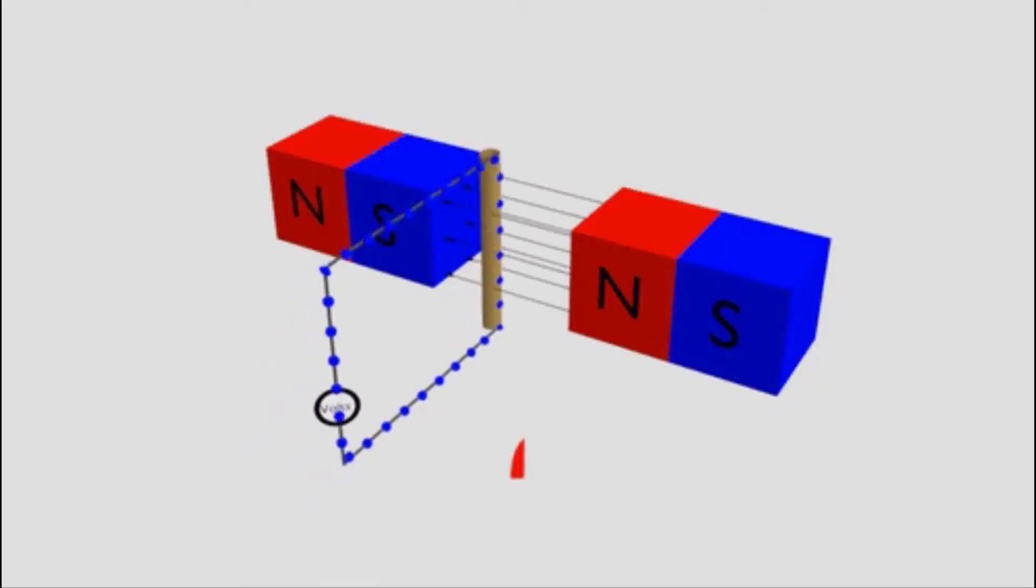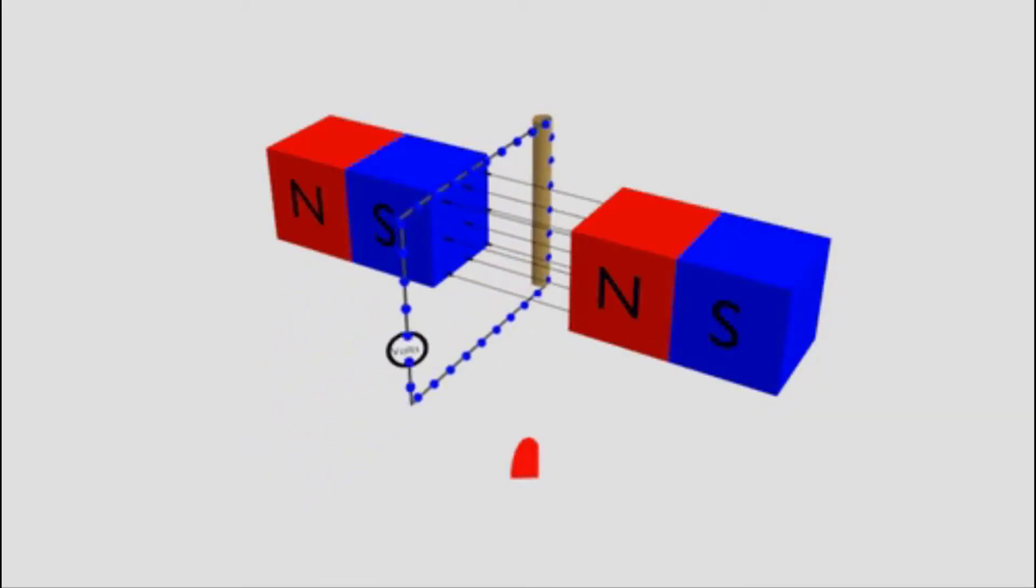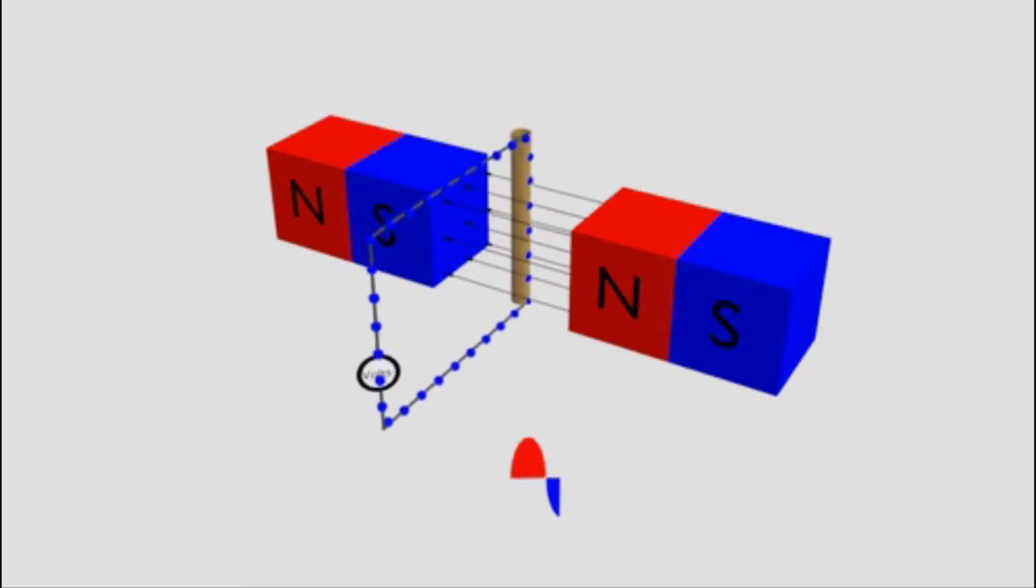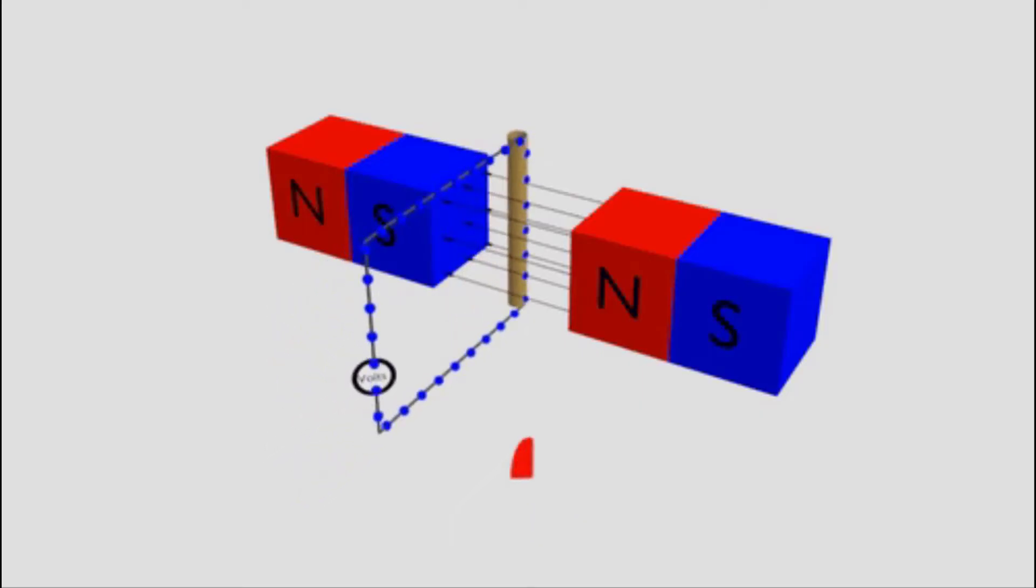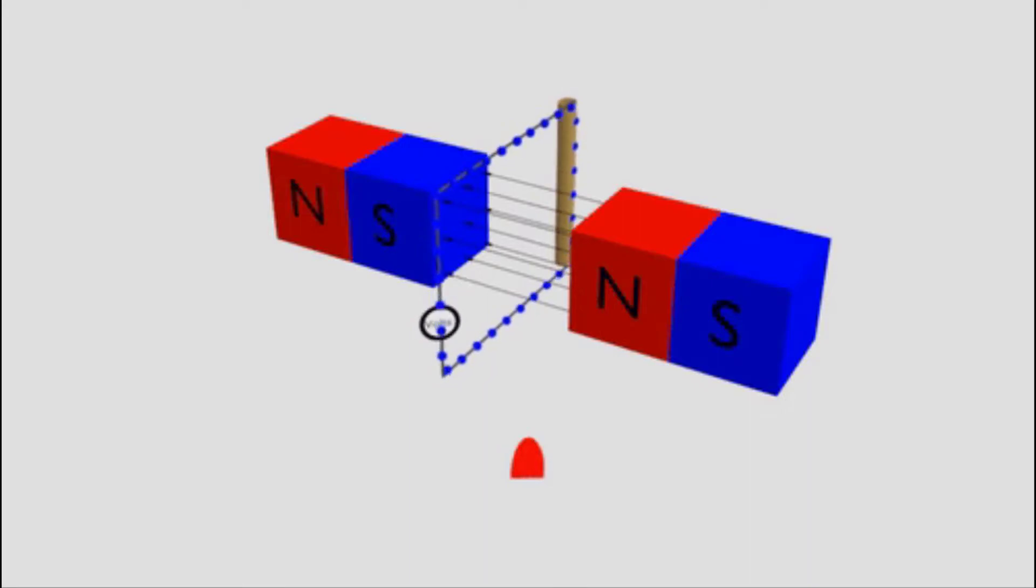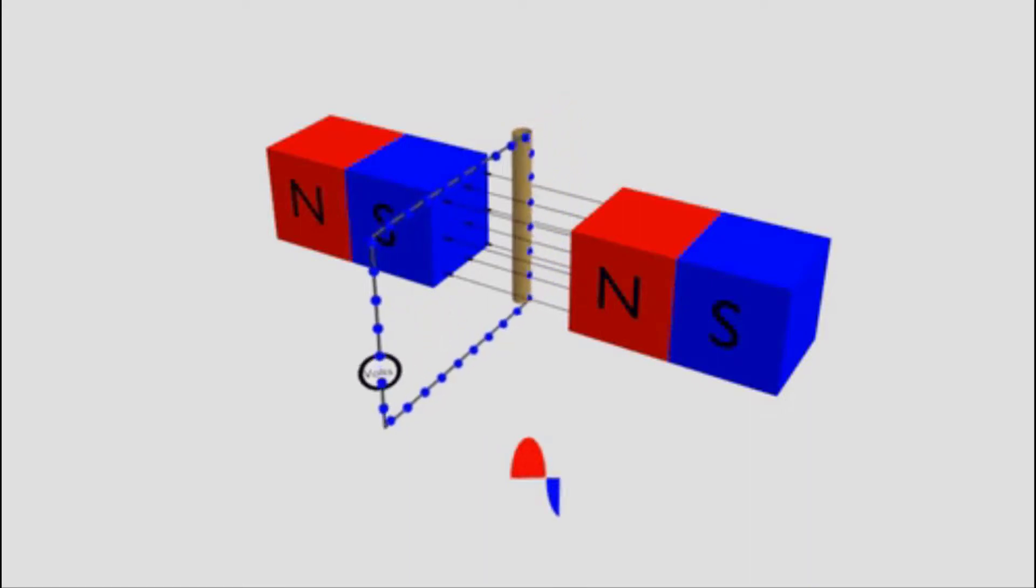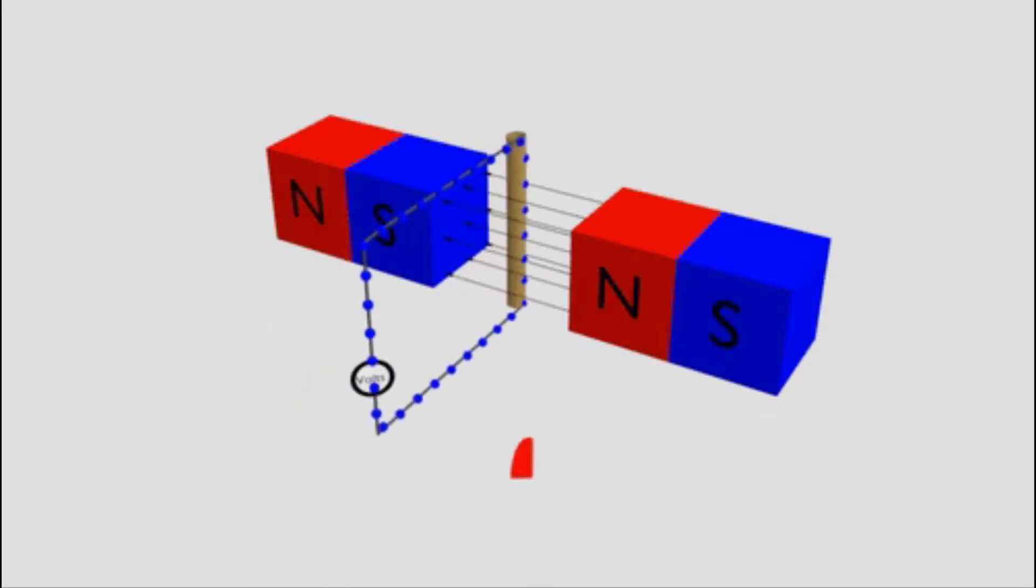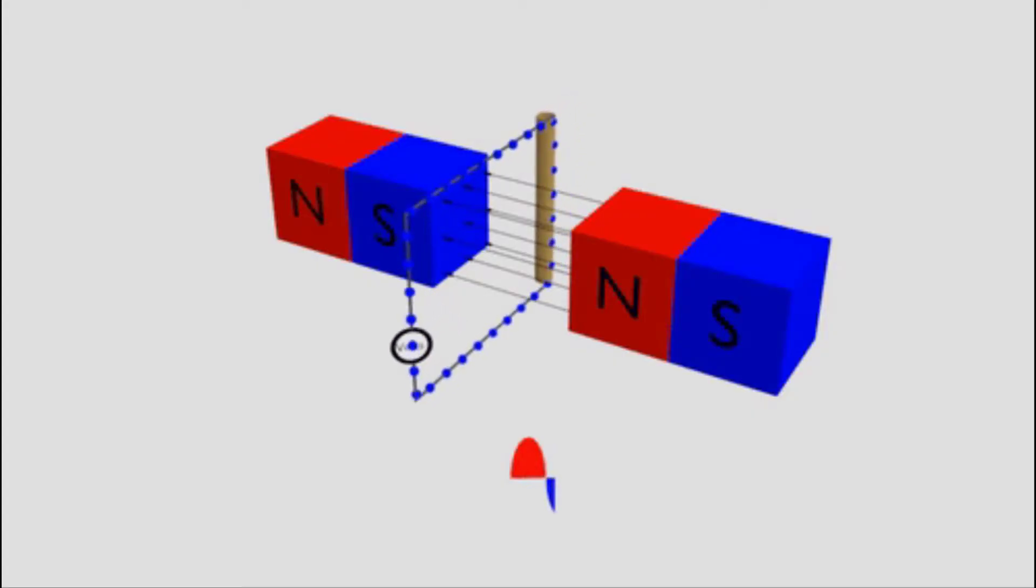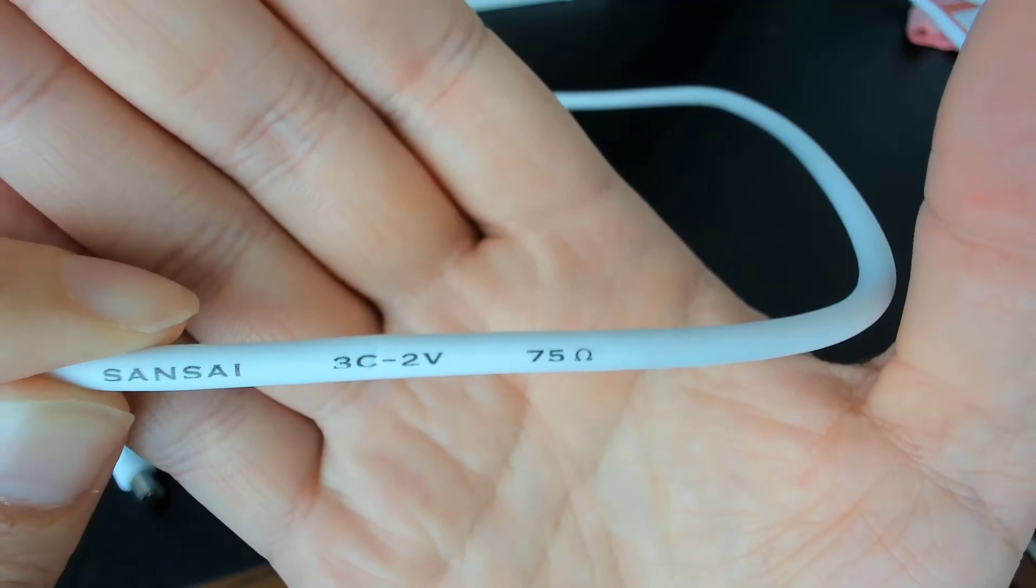So impedance is not only made up of resistance but also reactance. Reactance is the opposition to the movement of electric charge that arises from the changing magnetic and electrical fields in the circuits carrying alternating currents. So we've talked about the electromagnetic fields that are created within the cable - that has an effect on the flow of the electrons through the cable. And these two things together - resistance and reactance - give the cable its impedance rating.